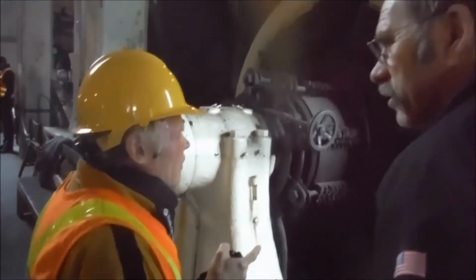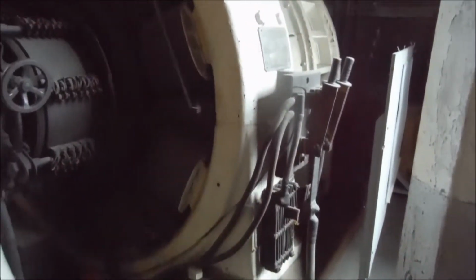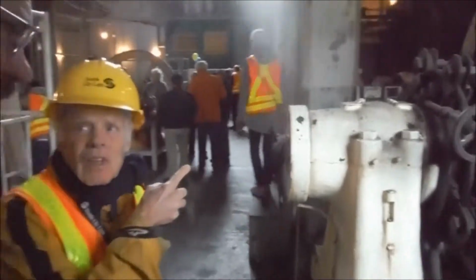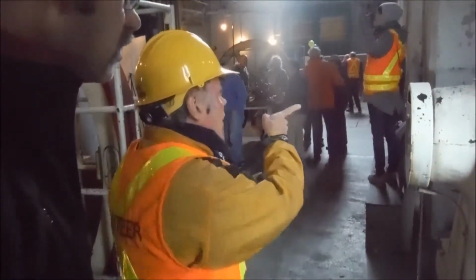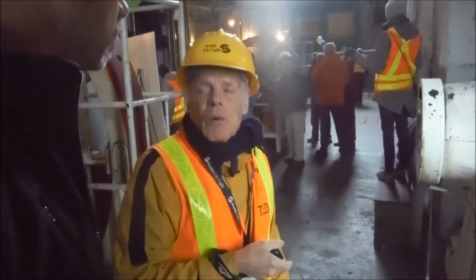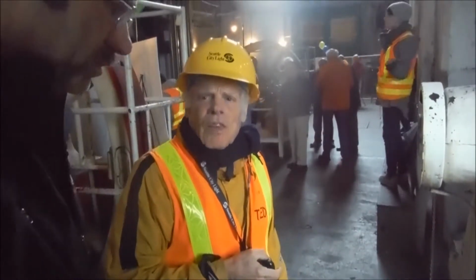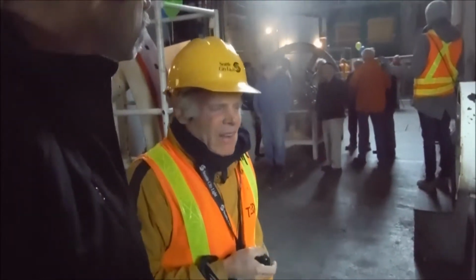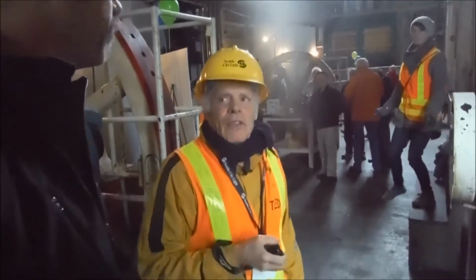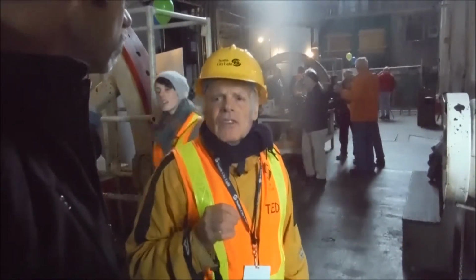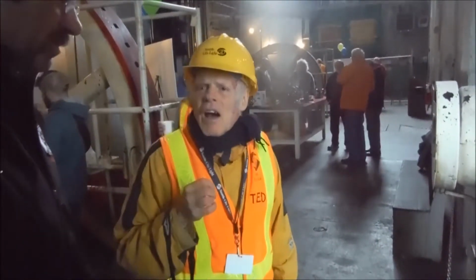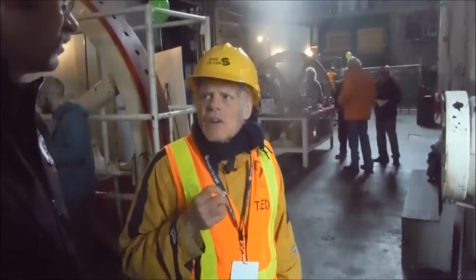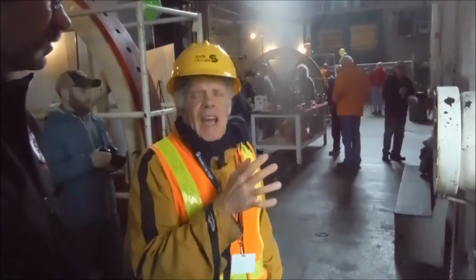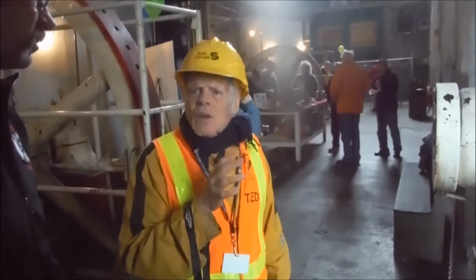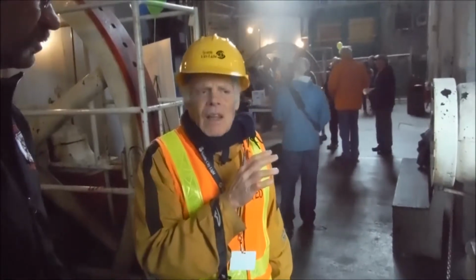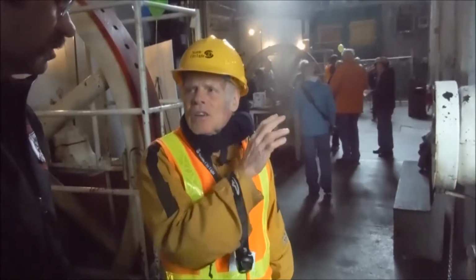They're disconnect switches, both for the output and also for the equalizer bus, because there's a second unit right beside that one over there. There were 2 of them, and both could produce 1 megawatt. Okay. And so the equalizer was for paralleling them? Yeah, because if the field excitation is too high on one, you could get circulating current, so the equalizer bus connected the 2 series fields to divert excess field current on the stronger unit over to the weaker unit.